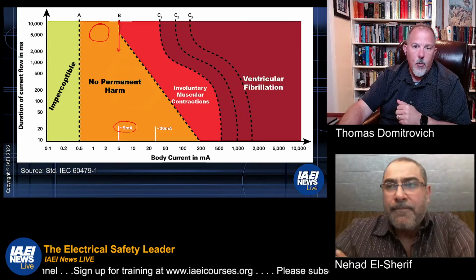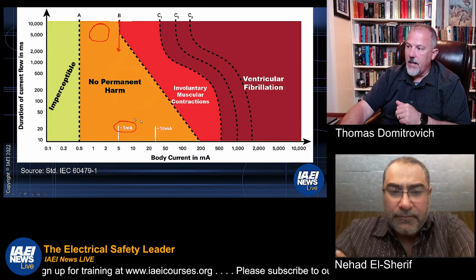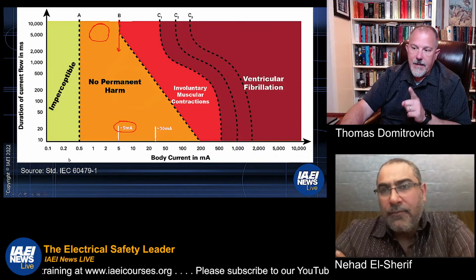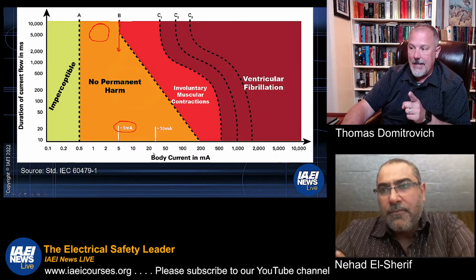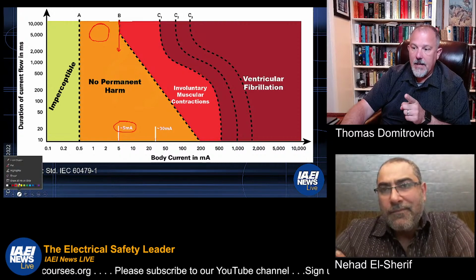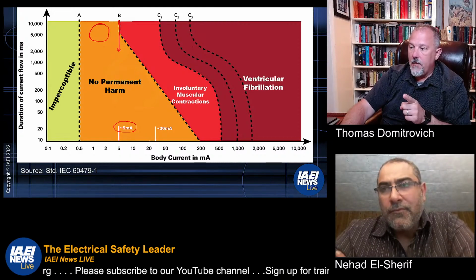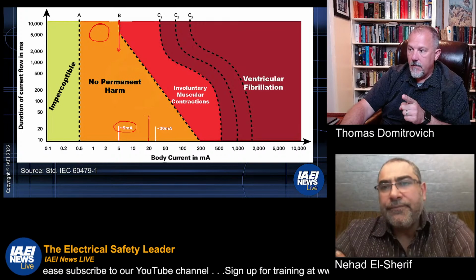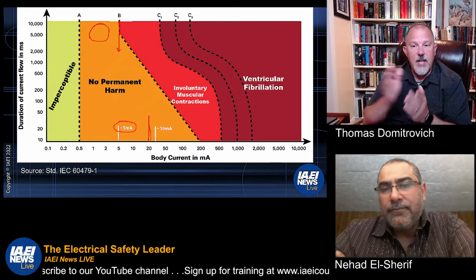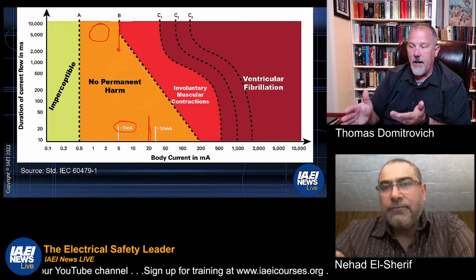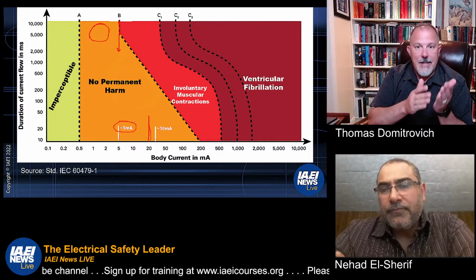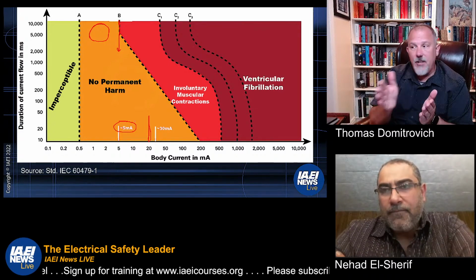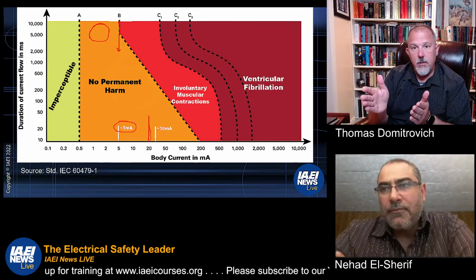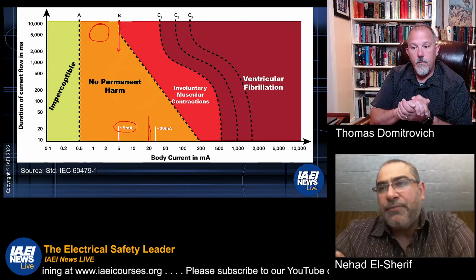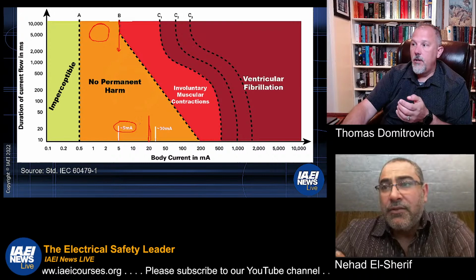Okay, so when we were talking about this earlier slide, remember, you're saying that the Class C and D devices pick up at 20 milliamps right here. Right. And they follow the same equation for trip times as a Class A GFCI, but you just increased the threshold. Yeah. You're delaying your starting point, pretty much. Like instead of starting at 6, you're starting at 20.